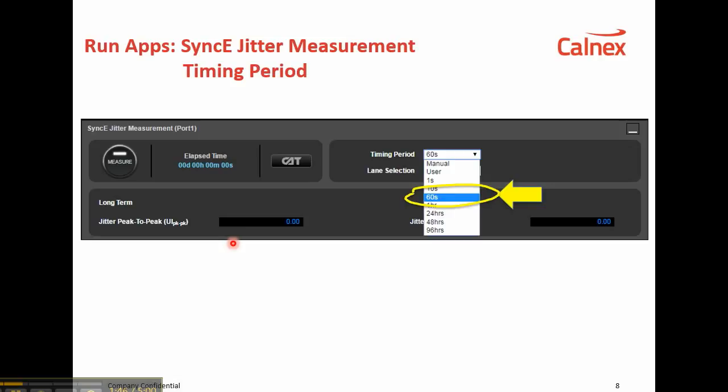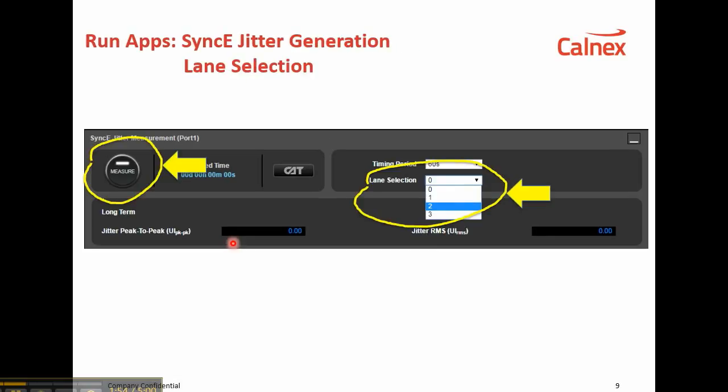Now G.8262 requires jitter to be measured over a full 60-second period, so choose a timing period of 60 seconds as shown here. On an LR4 signal there are four 25G lanes — it makes sense to measure jitter on all four lanes as they may not all be the same. Note that on an SR10 signal there are 10 lanes to measure.